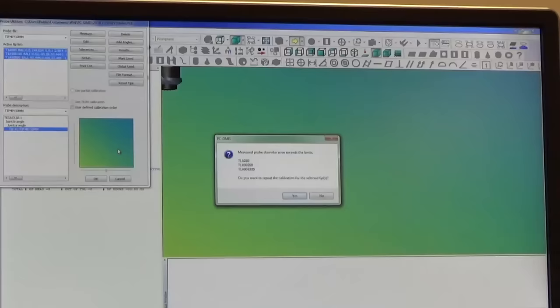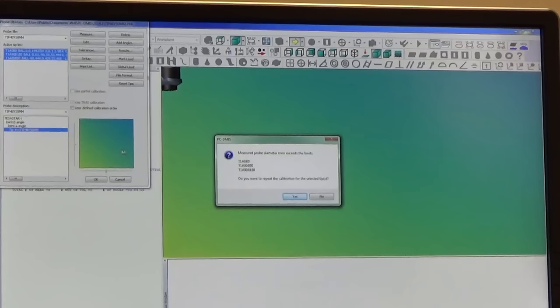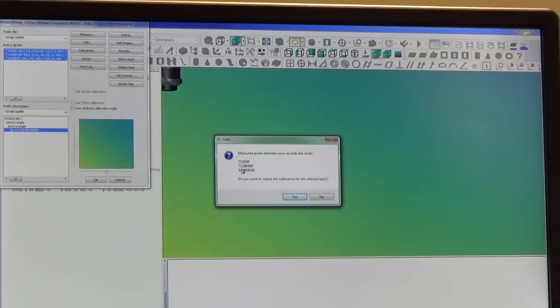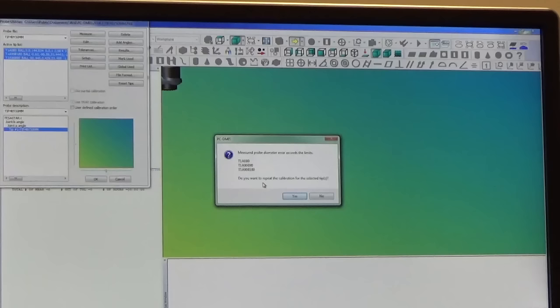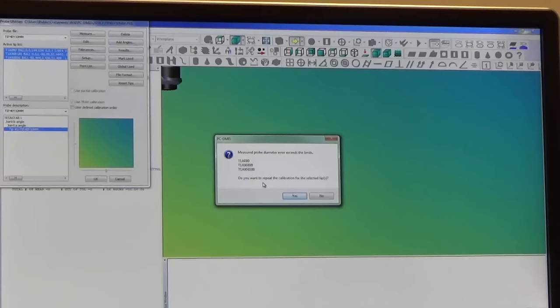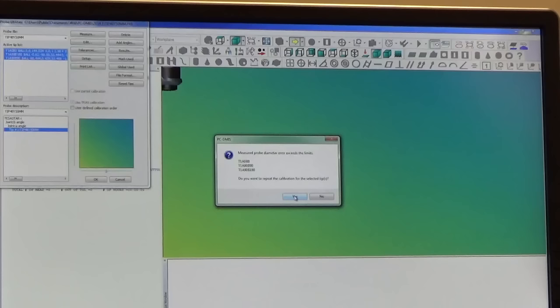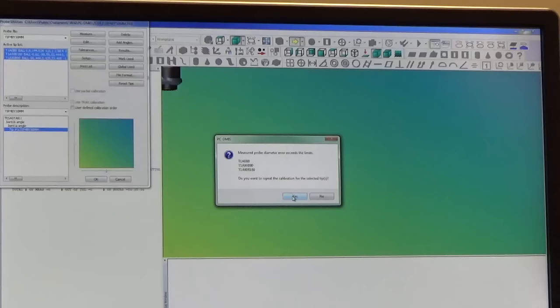Let's see what it says. So it tells us measured probe diameter error exceeds the limits for all three of those angles, which is really not the result that you're looking for. If you really want everything to check out perfectly and have no errors at all. So the bottom line is here, I have to go back through and repeat this calibration in order to get it to be complete. It's asking me right now, do you want to repeat the calibration for the selected tips? Yes, I of course do want to complete this.